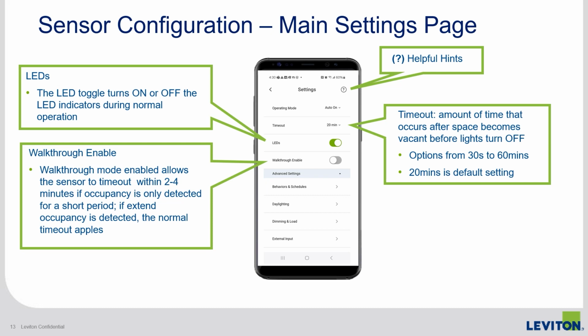There is also walkthrough mode, not to be confused with walk test mode. Walkthrough mode should be enabled for spaces that tend to have very short periods of occupancy, such as hallways or corridors where people are passing through. If enabled, the sensors will time out in roughly 2 minutes after vacancy versus the normal timeout setting. If the sensor sees extended occupancy, then the normal timeout will apply.